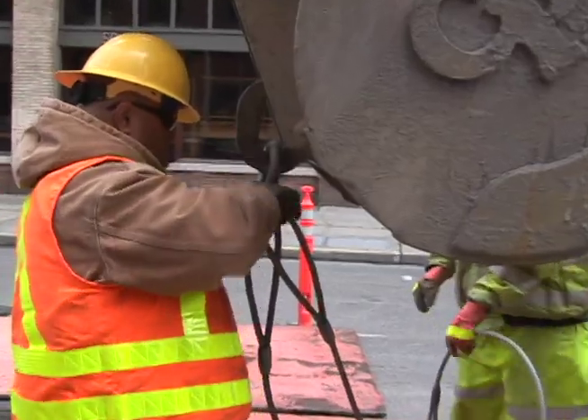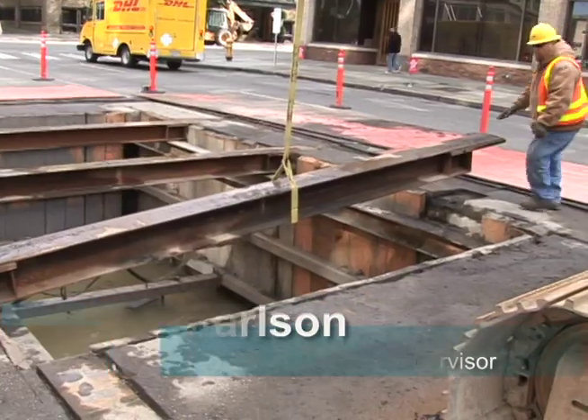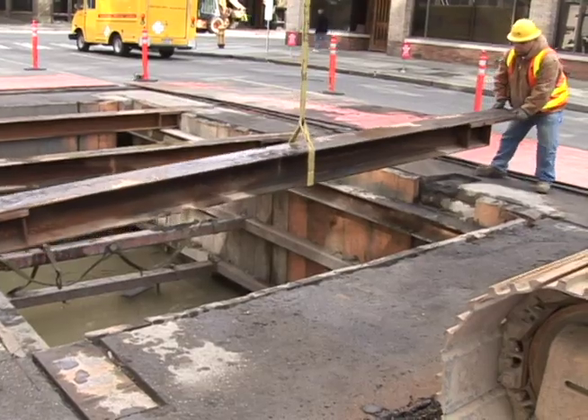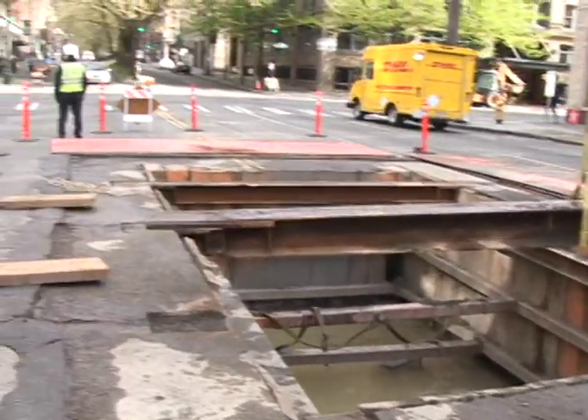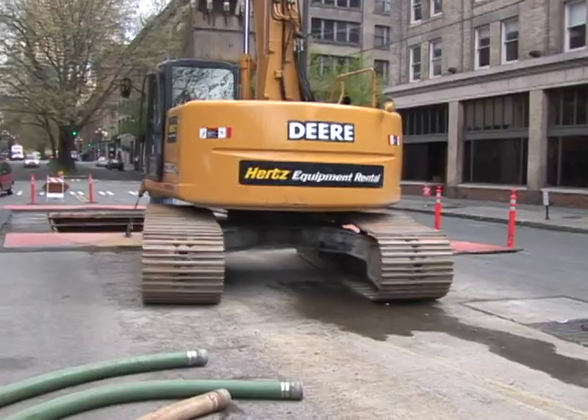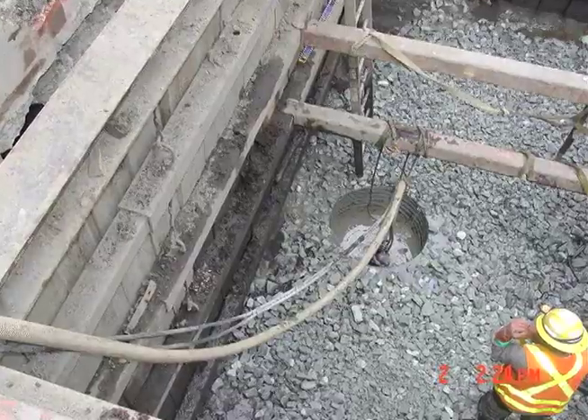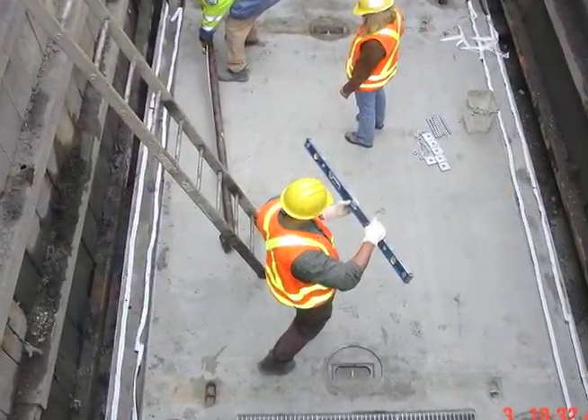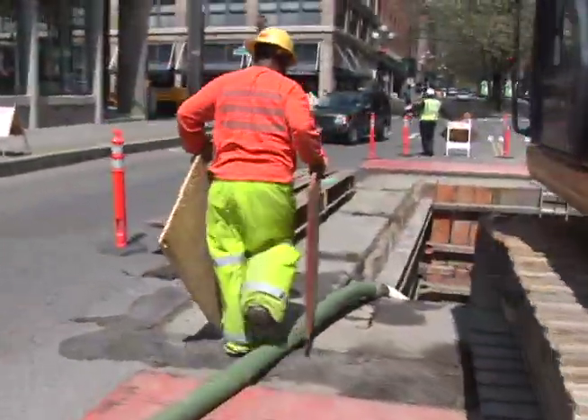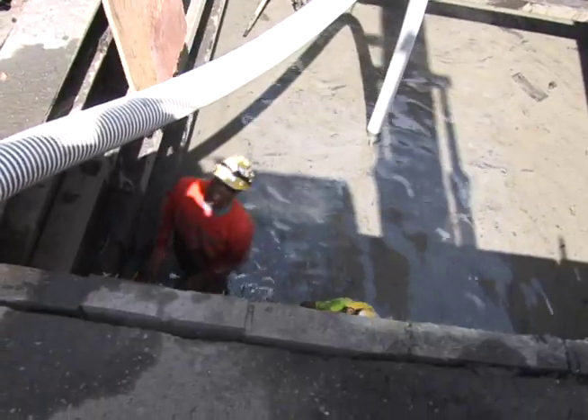This work is done by City Light's civil construction crews. We do basically all the heavy work, the really manual heavy work. Excavate, shore, site safety, pedestrian safety, vehicular safety. Shoring is a safety must when digging a deep hole. We go 15 feet, 16 feet deep, and you got vertical walls, so it's hard to hold vertical dirt and sand without it. I mean, it'd be almost impossible. And we'd be having cave-ins and things like that if we did not shore it properly.